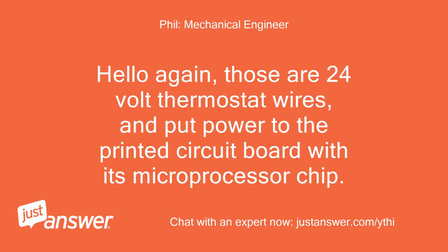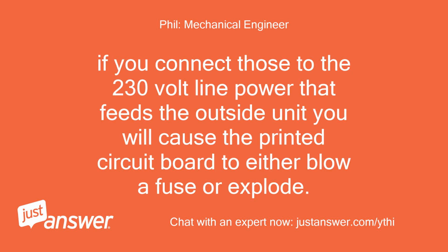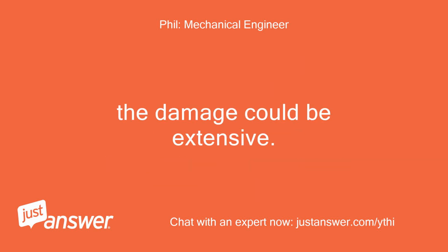Hello again, those are 24-volt thermostat wires, and put power to the printed circuit board with its microprocessor chip. If you connect those to the 230-volt line power that feeds the outside unit, you will cause the printed circuit board to either blow a fuse or explode. The damage could be extensive.